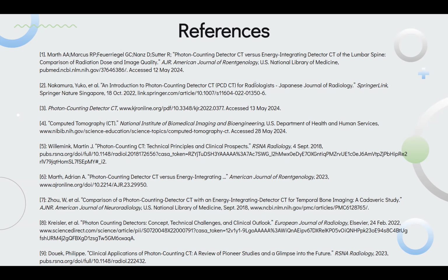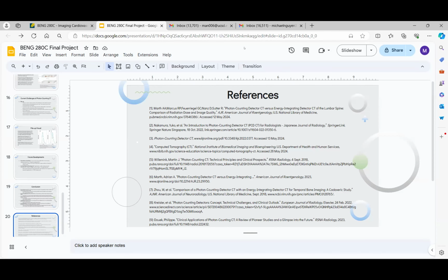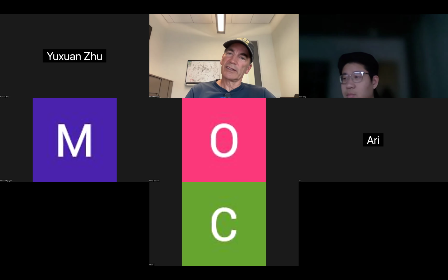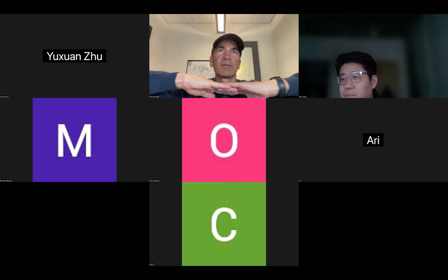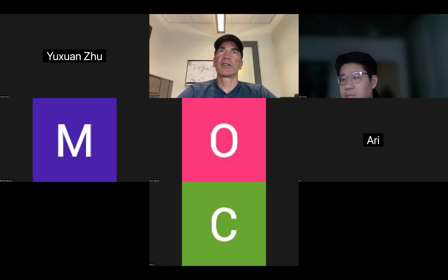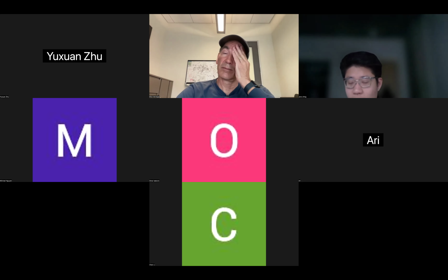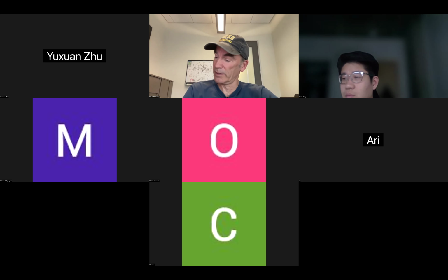Thanks very much for that review of photon counting. What's interesting is that the MTF data you showed seemed to be in the two-dimensional plane, and the slice direction was dealt with as a separate dimension, as opposed to looking at the MTF in that direction as well. If you were to redo that study, you would probably image things in, say, the coronal plane and measure the MTF in, say, the XZ direction as well. That would show a much better MTF for the PCCT.